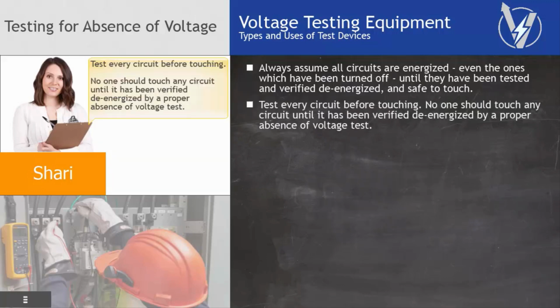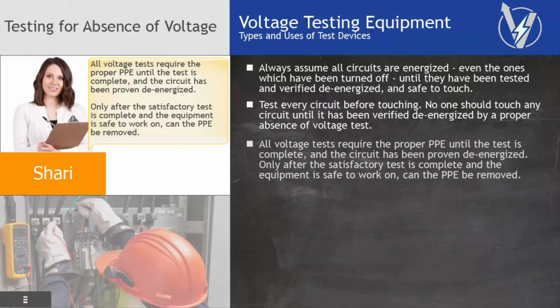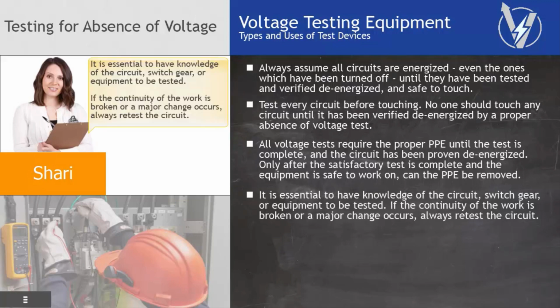Test every circuit before touching. No one should touch any circuit until it has been verified de-energized by a proper absence of voltage test. All voltage tests require the proper PPE until the test is complete and the circuit has been proven de-energized. Only after the satisfactory test is complete and the equipment is safe to work on can the PPE be removed. It is essential to have knowledge of the circuit, switchgear, or equipment to be tested. If the continuity of the work is broken or a major change occurs, always retest the circuit.